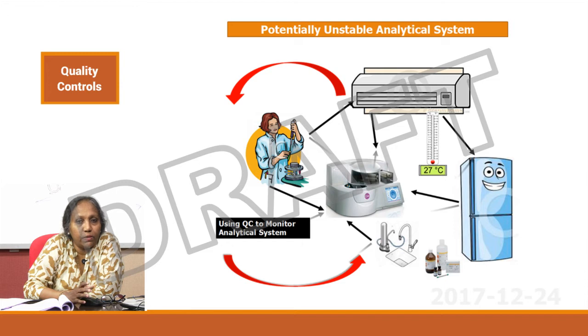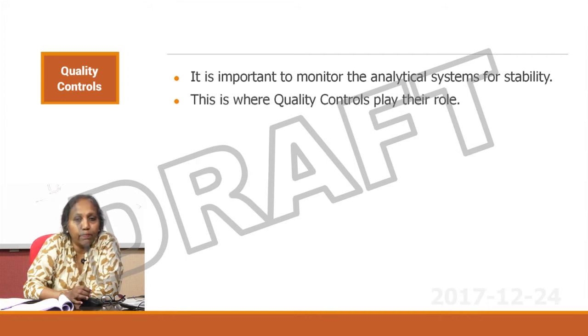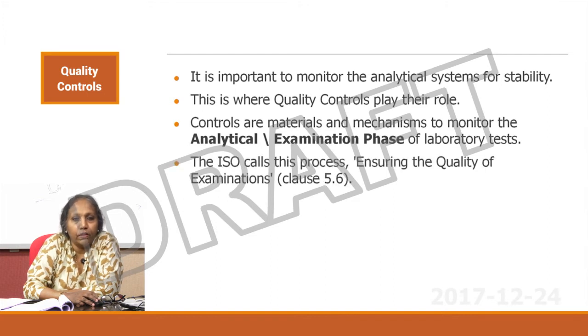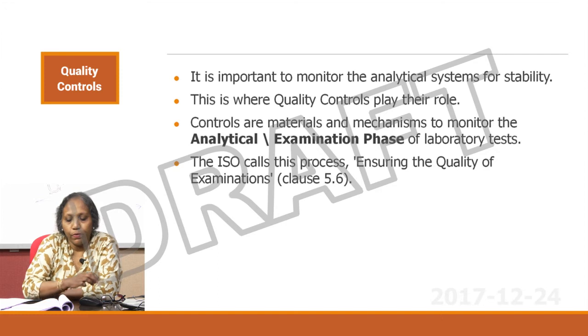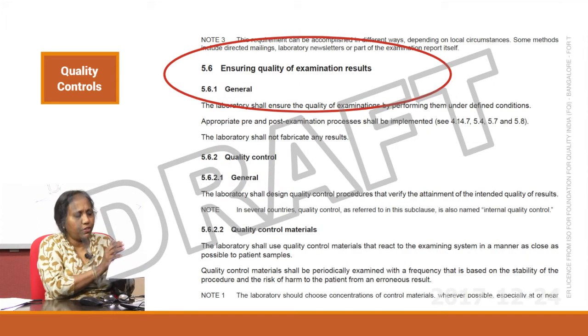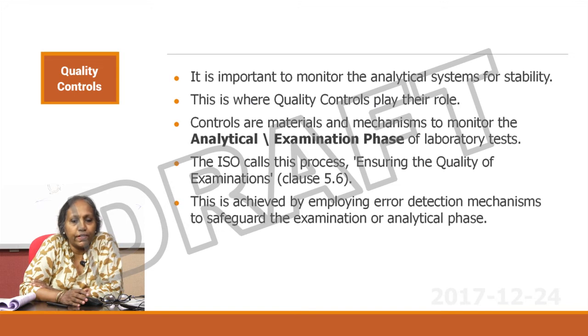So let us call it potentially unstable analytical systems. It is thus important to monitor the analytical system for stability, and this is where quality controls play their role. Controls are materials and mechanisms to monitor the analytical or the examination phase of laboratory tests. The ISO calls this process ensuring the quality of examination under clause 5.6, which is about ensuring the quality of examinations.